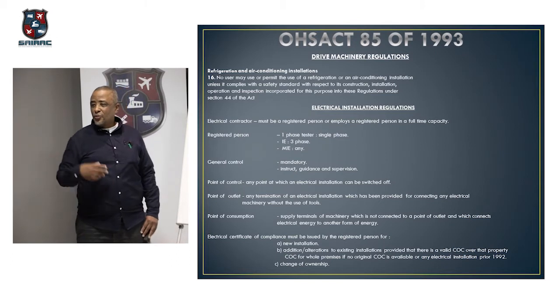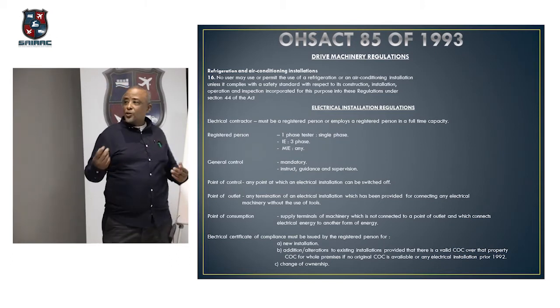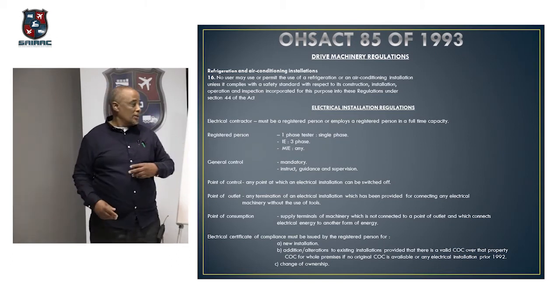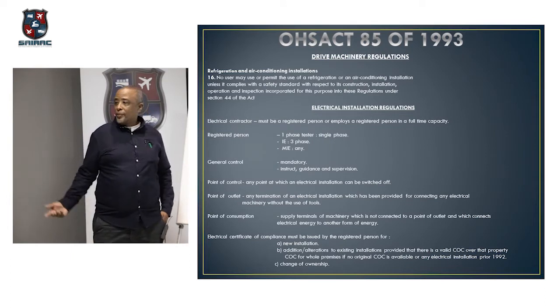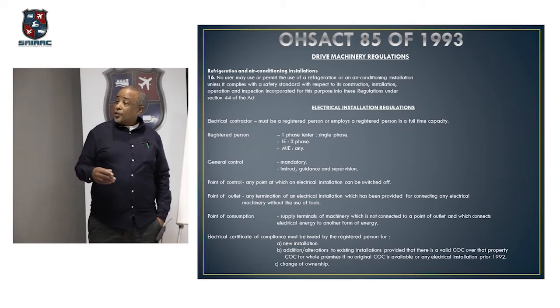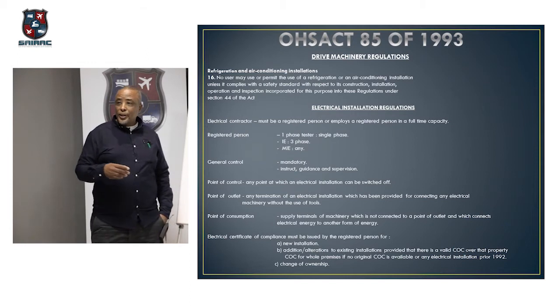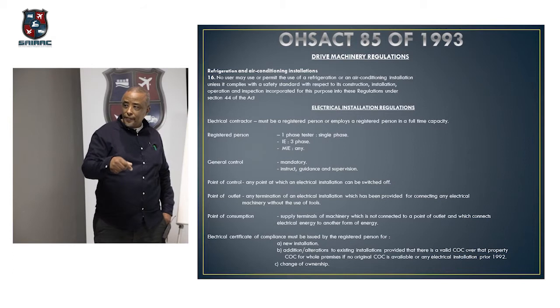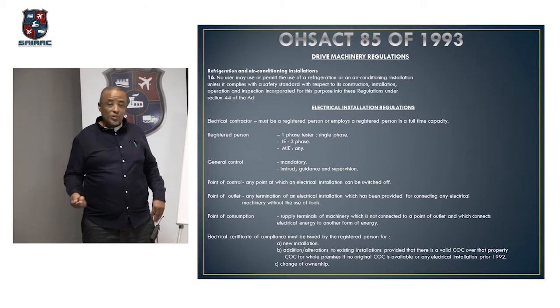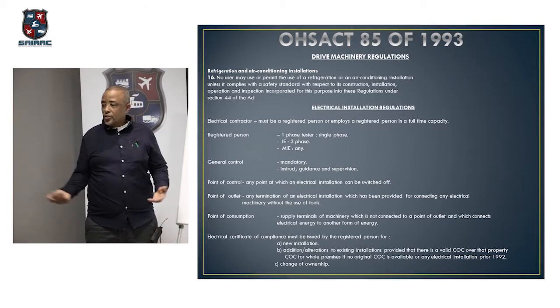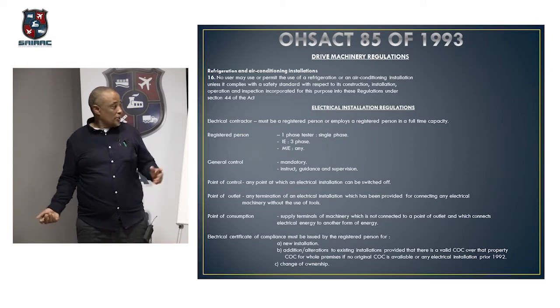Any new installation, if he feels he's happy, no wires still hanging. We can't do every inspection. If you do a random inspection and you find the guy's asked for a service and there's still cables hanging, we don't give it to him, because he's unable to give a certificate. City of Cape Town works a bit different to our municipality, where City of Cape Town will say we want a certificate first before we put the power on. That's very wrong, because what test are you going to do there? It's only your earth test, only your dead test. Okay, so we don't accept that.